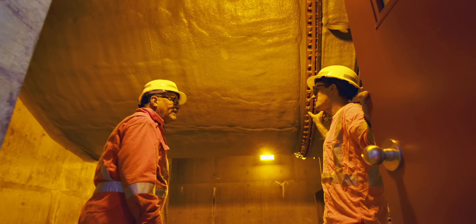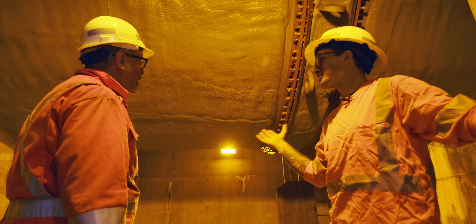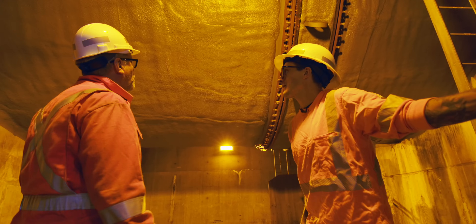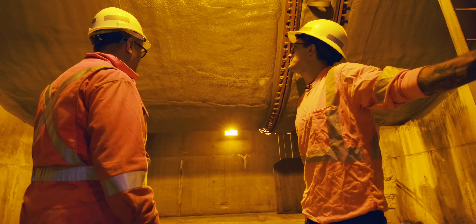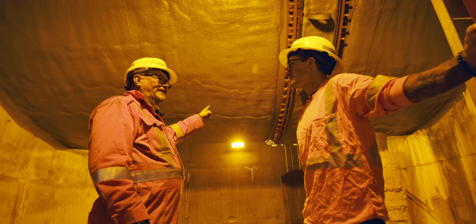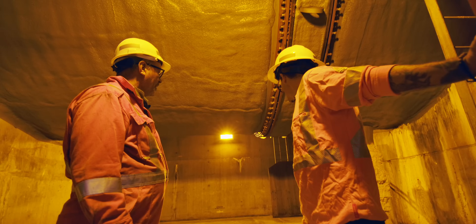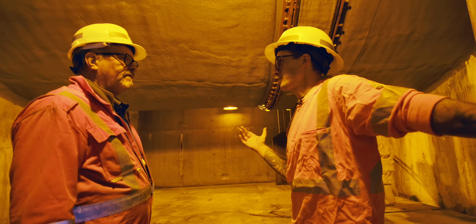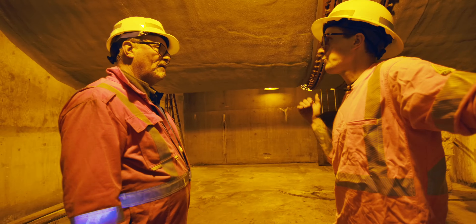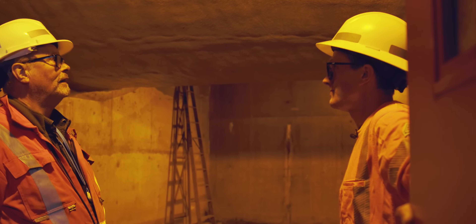We have the shift ring in here, which allows for thermal expansion and contraction. It is not dripping very much. Presumably the pressure of the water in there is huge. Yes, it is. This location here is the penstock drain valve — essentially when we're isolating the unit and we've shut the intake gate, this is where we run the water out of that penstock so everything's draining for worker safety.